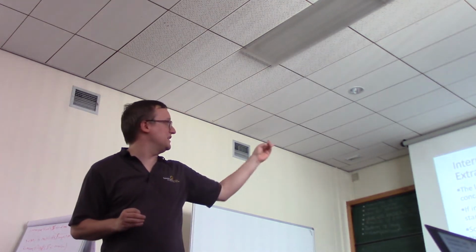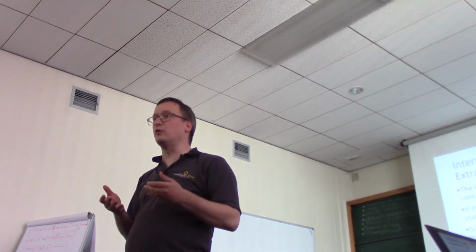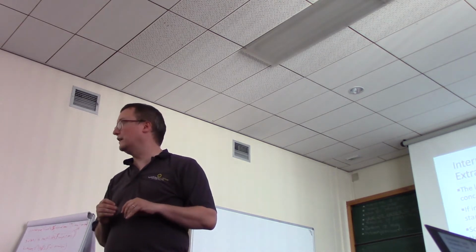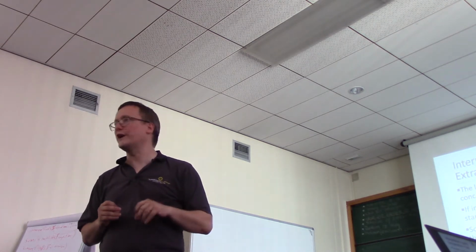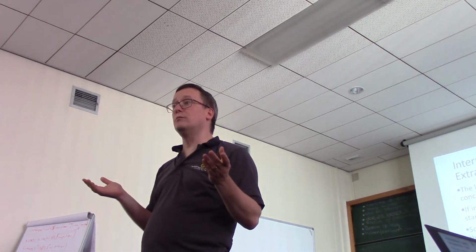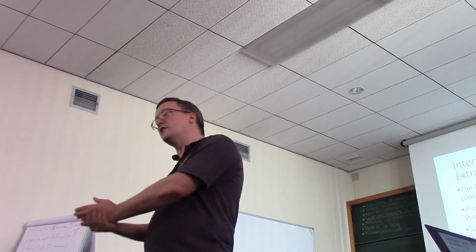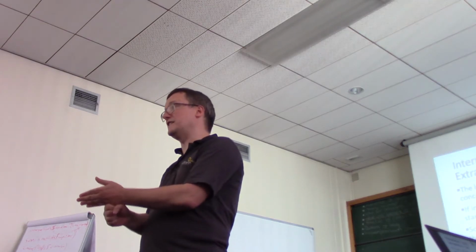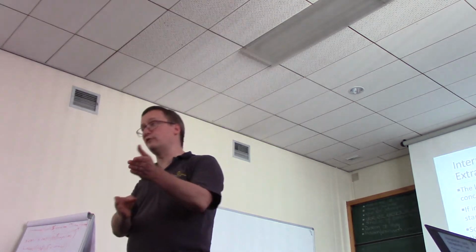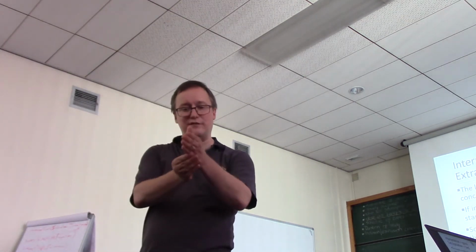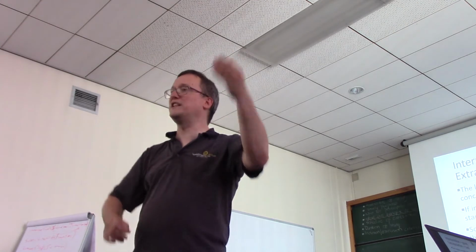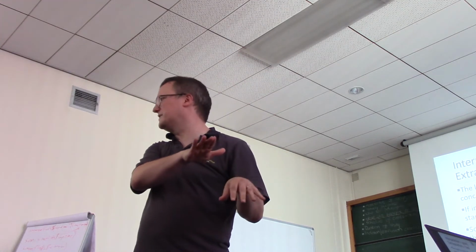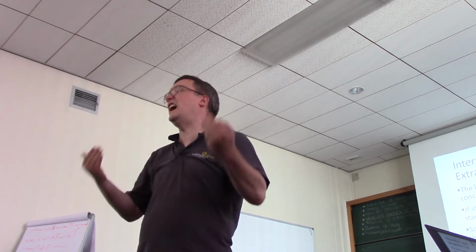So in the case of the Luminex platform, you're typically going to see something that looks like OOR less than or OOR greater than. These are out of range. So it is possible that you have measured an intensity that's too low to be quantified. That's an extrapolation on the low end. It's out of range down. It may be that you have a concentration so great that the intensity is in this blasting zone, basically, for intensity. That creates an out of range high.